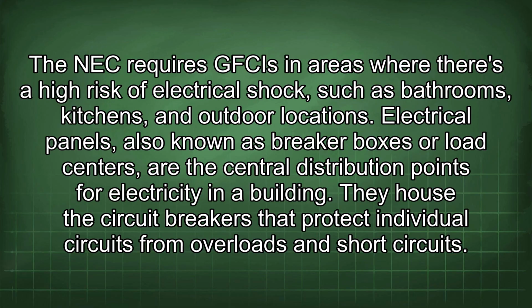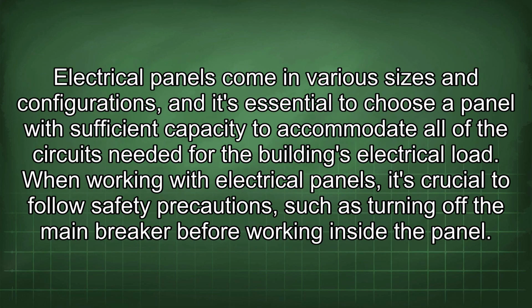Electrical panels, also known as breaker boxes or load centers, are the central distribution points for electricity in a building. They house the circuit breakers that protect individual circuits from overloads and short circuits. Electrical panels come in various sizes and configurations, and it's essential to choose a panel with sufficient capacity to accommodate all of the circuits needed for the building's electrical load. When working with electrical panels, it's crucial to follow safety precautions such as turning off the main breaker before working inside the panel.